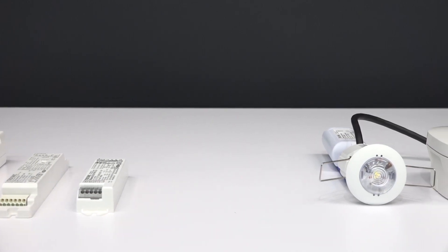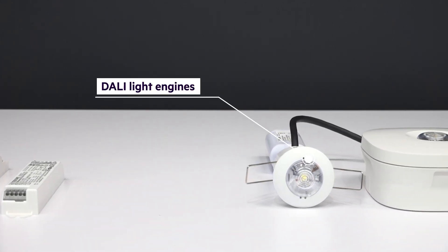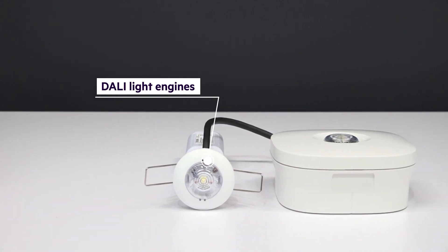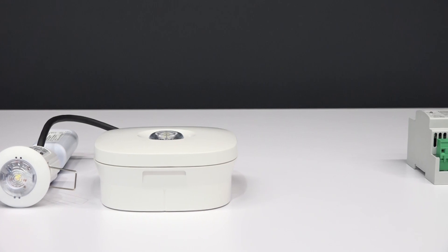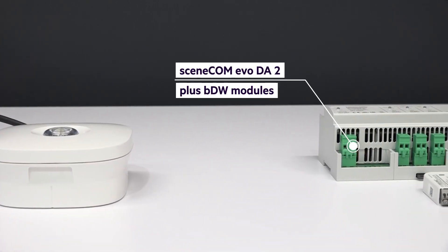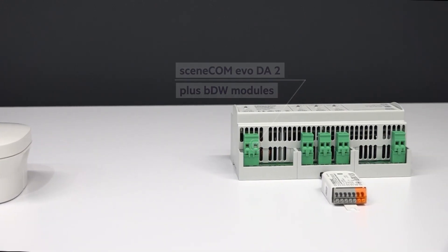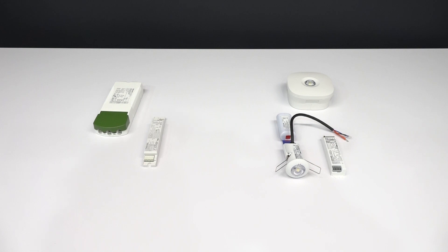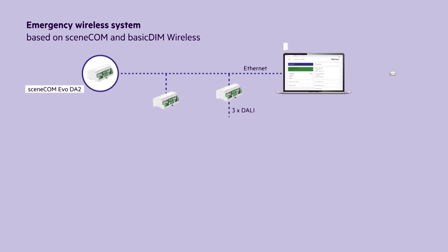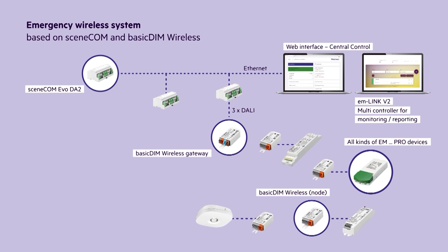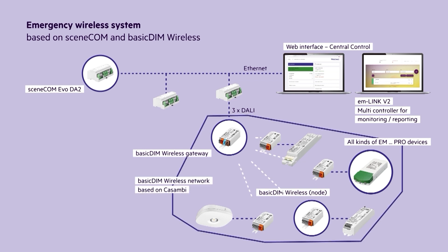All existing Tridonic DALI emergency drivers and light engines can be used to build up wireless emergency systems. Depending on the integration of the DALI power supply in the emergency driver, the passive or active basic DIM wireless module is used as a node to enable wireless communication within the luminaire. The basic DIM wireless DALI gateway on the side of the sceneCOM evo DA2 enables the connection between the wired and the wireless network.